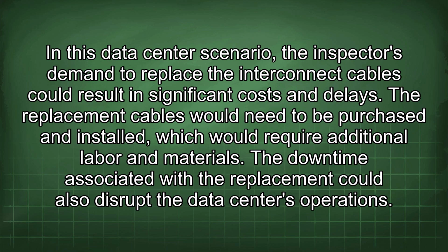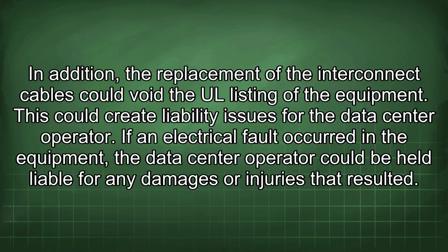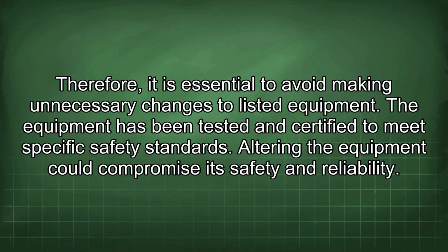The downtime associated with the replacement could also disrupt the data center's operations. In addition, the replacement of the interconnect cables could void the UL listing of the equipment. This could create liability issues for the data center operator. If an electrical fault occurred in the equipment, the data center operator could be held liable for any damages or injuries that resulted. Therefore, it is essential to avoid making unnecessary changes to listed equipment.